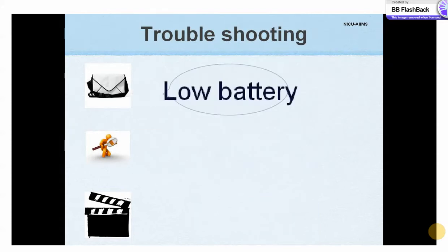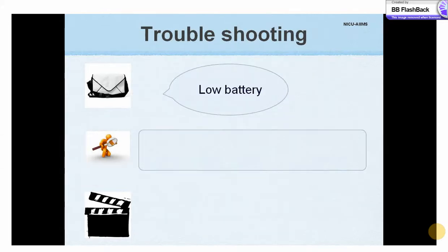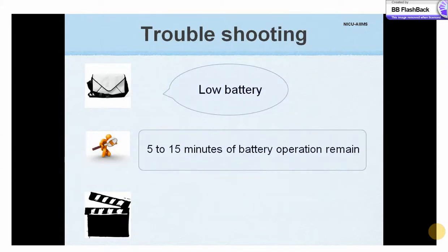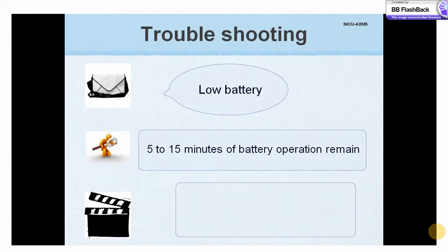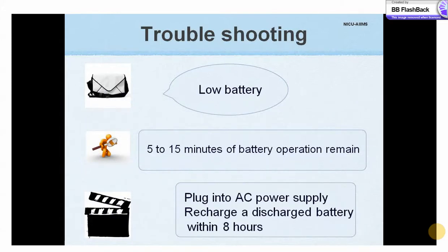A low battery message indicates only 5–15 minutes of remaining battery power. Plug the oximeter into the AC power supply. To prevent permanent damage to the battery, recharge a discharged battery within 8 hours after the low battery message is displayed.